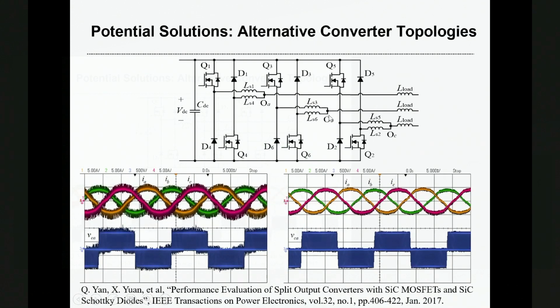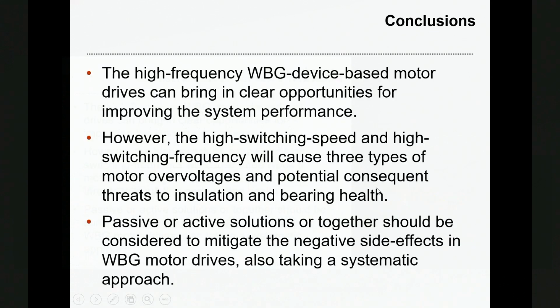There are other types of converter topologies. For example, this one has an embedded DVDT filter in the circuit, which helps to reduce the voltage overshoot and also reduce the harmonics in the current due to the capacitance charging of the cable.